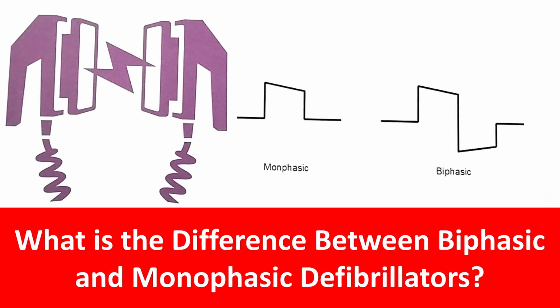In the cardiac catheterization laboratory, during electrophysiology studies, sometimes they use even two defibrillators simultaneously discharged to treat arrhythmias which are refractory. That is, dual defibrillator use simultaneously. So there are situations where higher energies are required. But usually monophasic maximum is 360, biphasic maximum is 200. And the higher the energy you deliver, the more is the myocardial damage. That is probably one reason why biphasic has an advantage now and monophasic has almost been phased out.